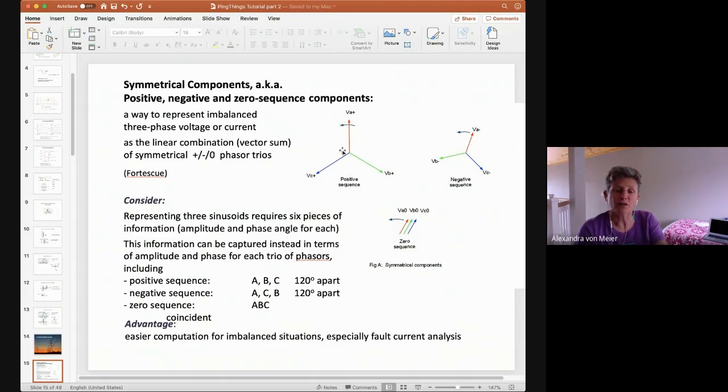So if you've defined what VA positive is, you've defined what VB and VC positive are. And in a balanced system, that's all there is. Now, when you have distortion in the system, because not the same number of customers are connected to each phase, some streets only have phase A. And in our EcoBlock project, we have all the customers on one street on one phase.